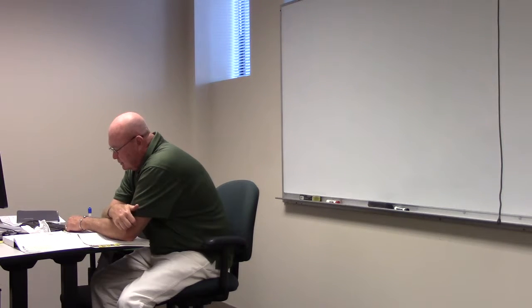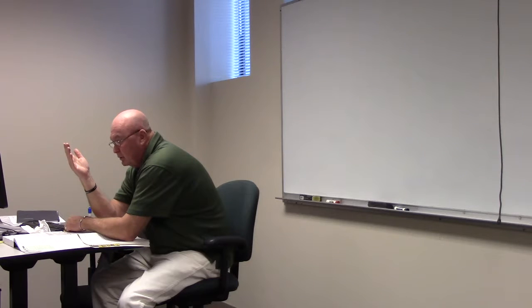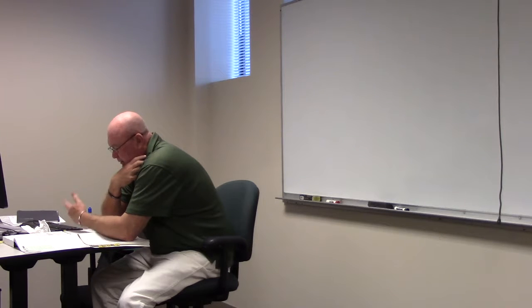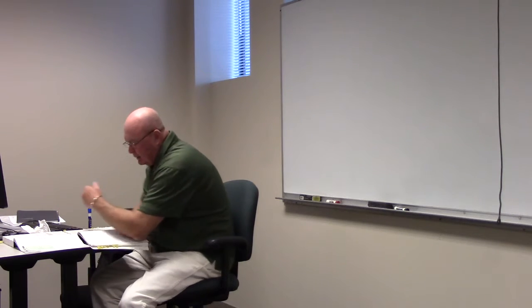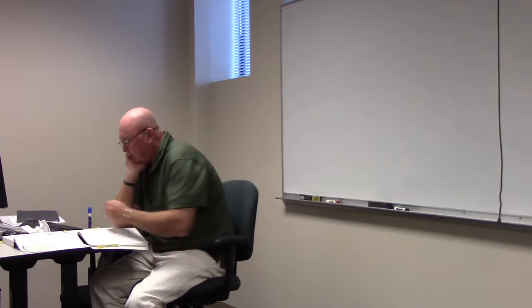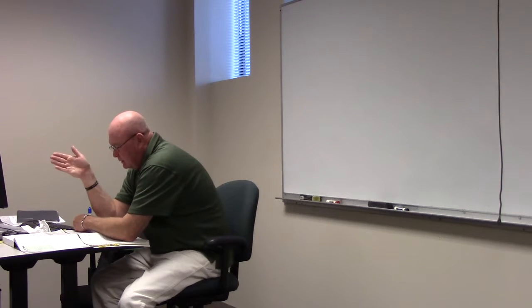3.1.2 General lighting loads. General lighting load is the main lighting used. It's like what we got here. This is a general lighting load. Within the building, additional lighting installed for accent, display, show windows, signs, all that's general lighting load. It is computed based on the type of occupancy. We know that. That's what we've been looking at, 220.12. For types of occupancies not listed in 220.12, the general lighting load should be calculated according to the NEC listed previously. That's probably important to remember.